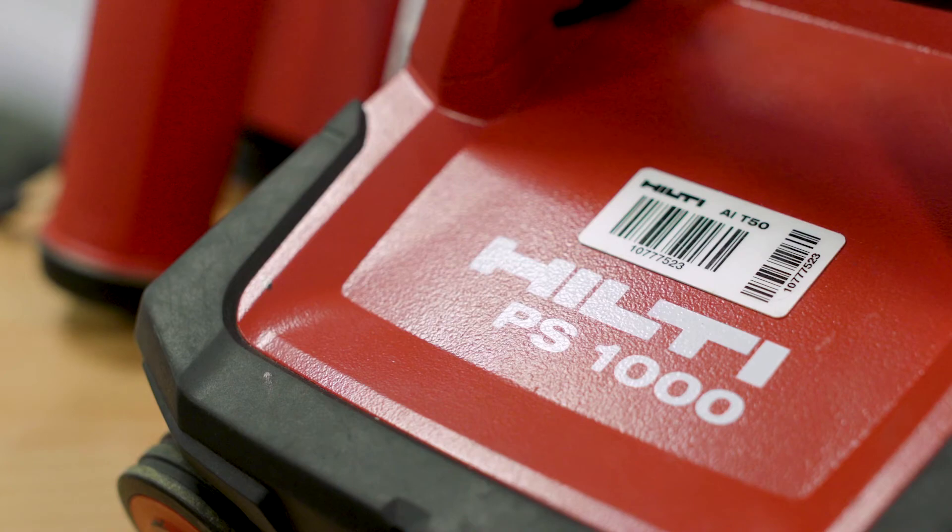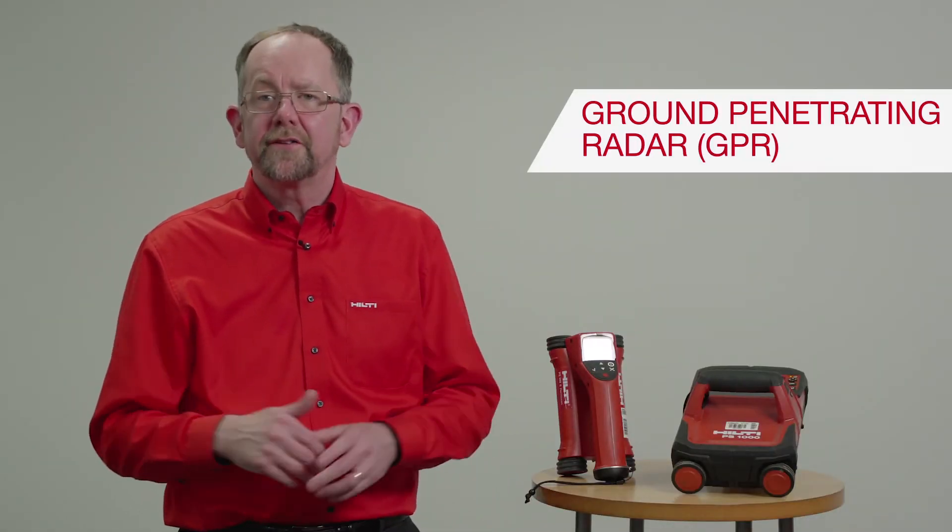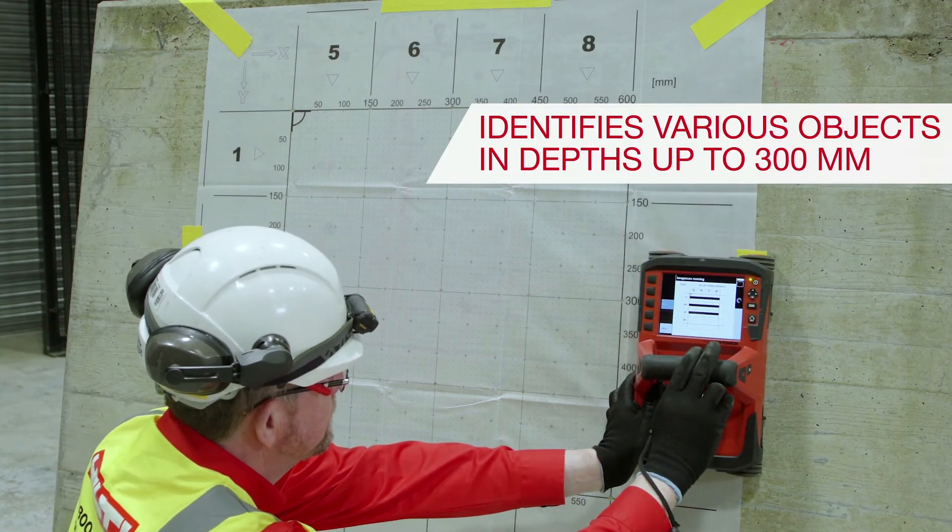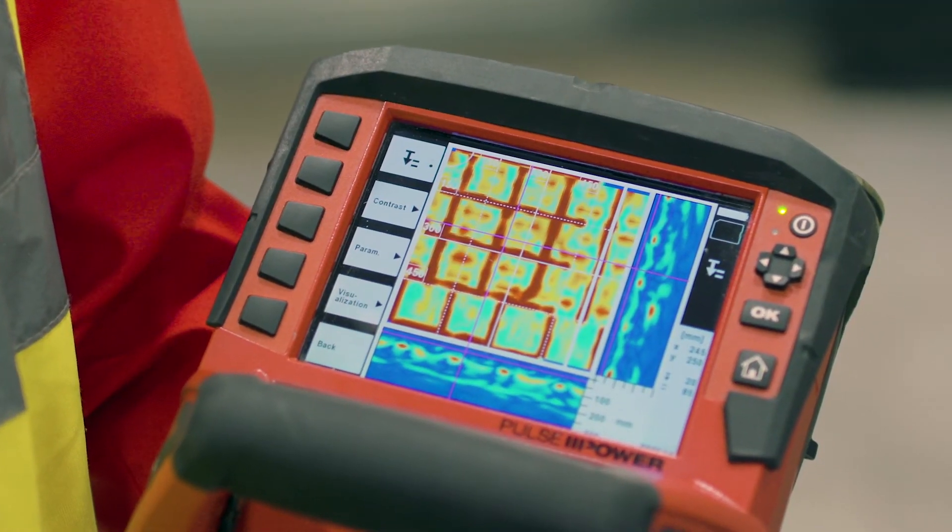The Hilti PS 1000 system operates on ground penetrating radar or GPR technology. This tool is ideal for localizing multiple object types at depths of up to 300 millimeters in reinforced concrete and other base materials.